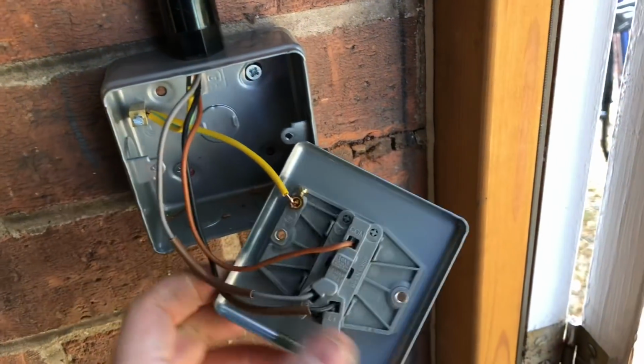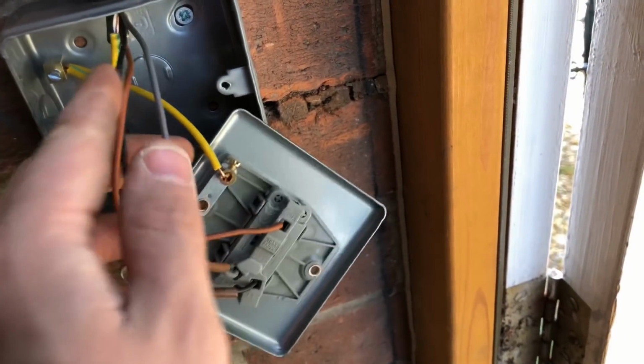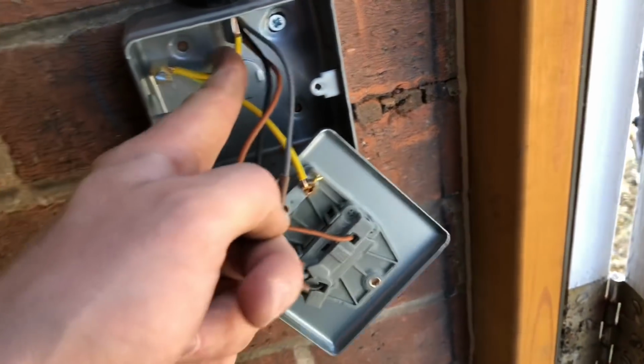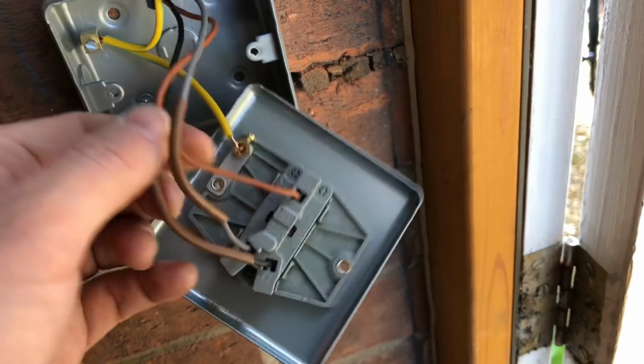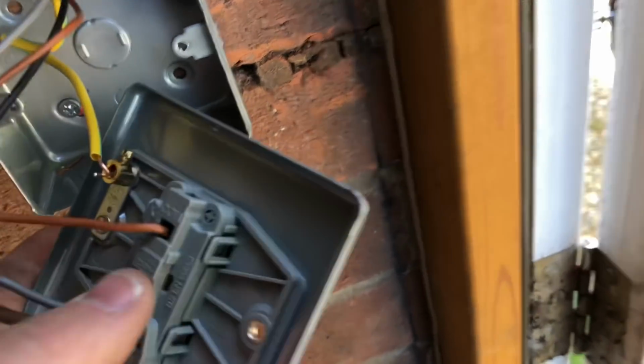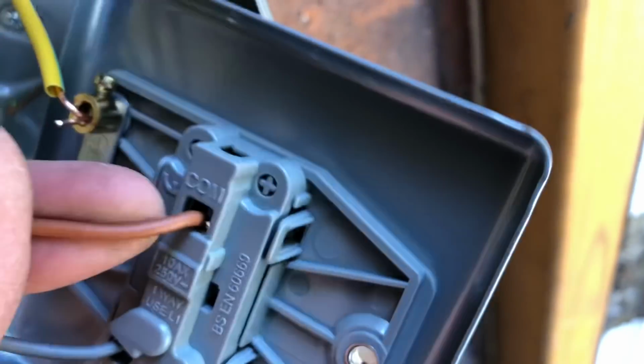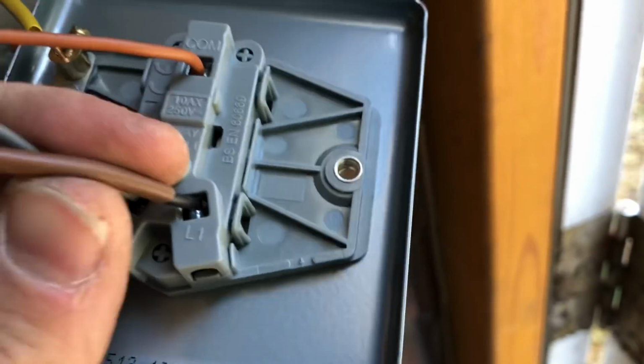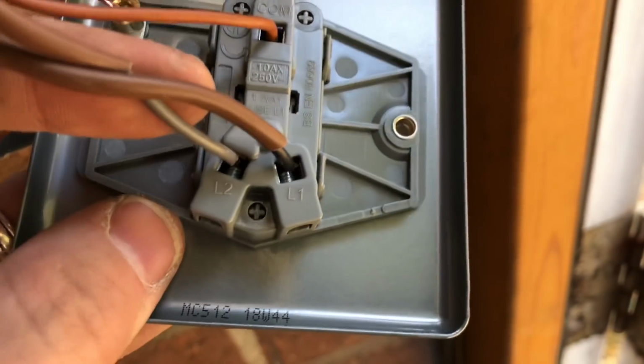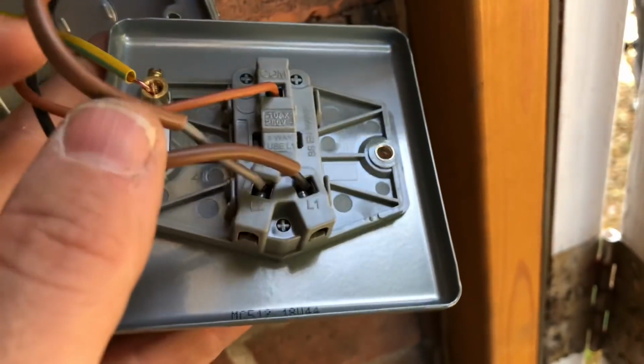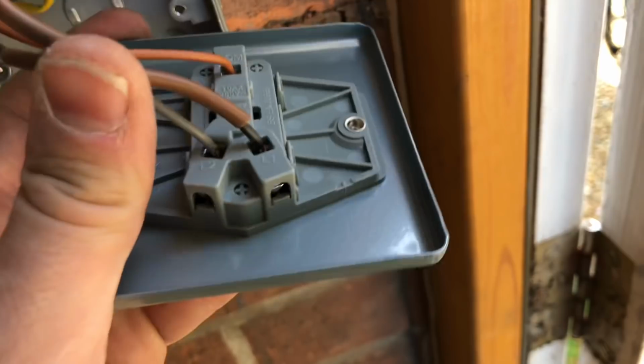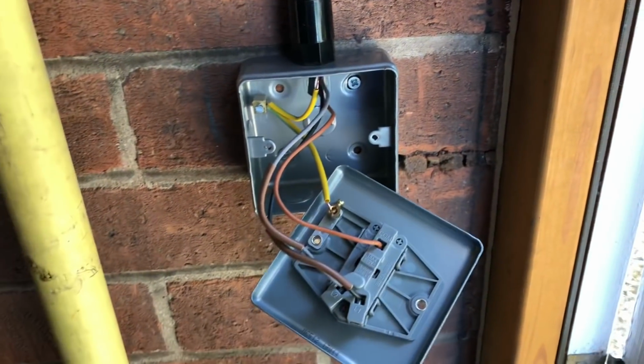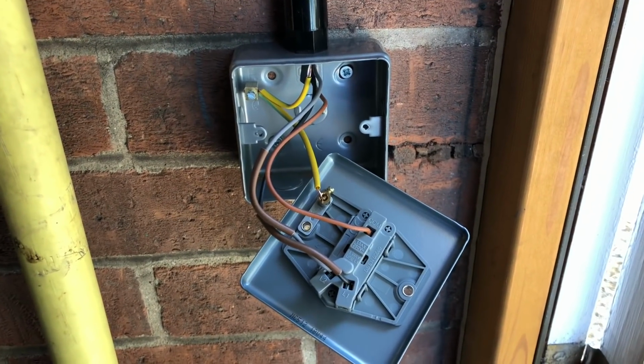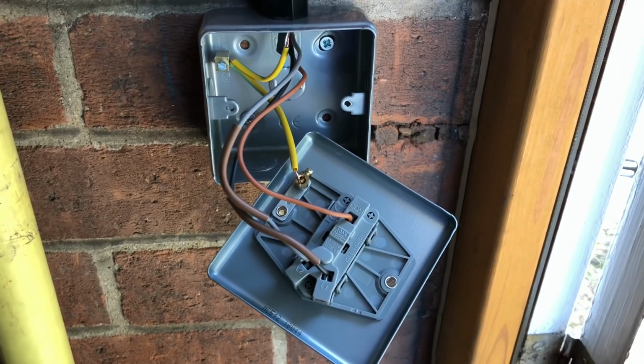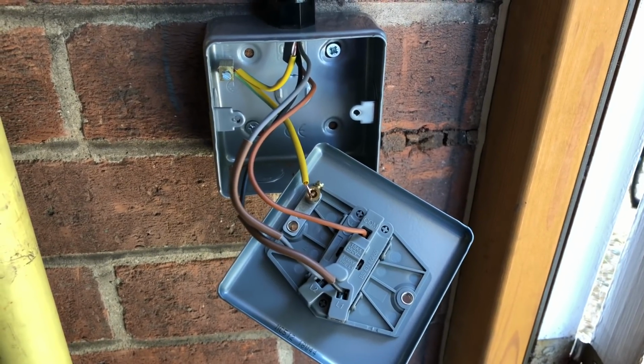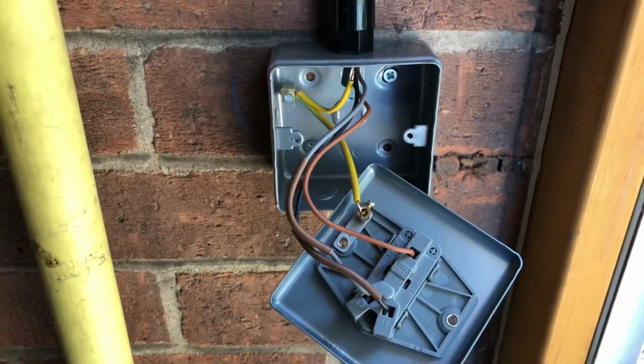So here's the new two-way switch I've installed. Metal clad two-way switch, surface mounted, with a 3-core and earth cable coming into it, 1mm 3-core and earth, and this is how I've connected it. I've got the brown into the common, black in L1, grey in L2, and both the black and the grey are sleeved with brown sleeving to show that they are live conductors. I've just looped the earth wire through the back box terminal and into the front plate terminal so that everything's earthed properly.